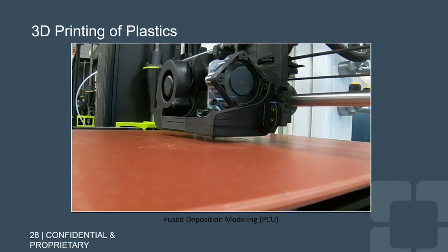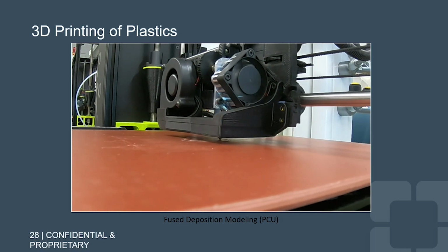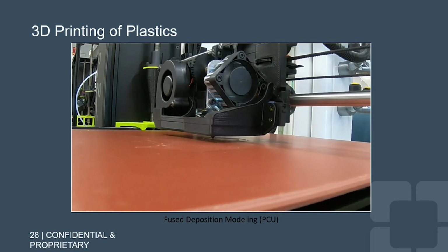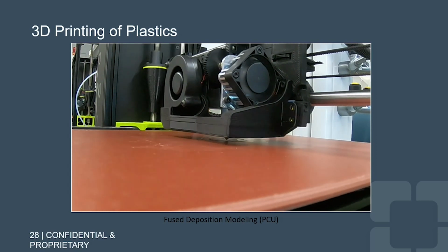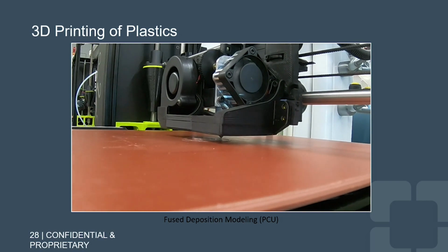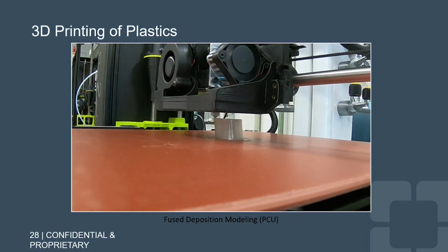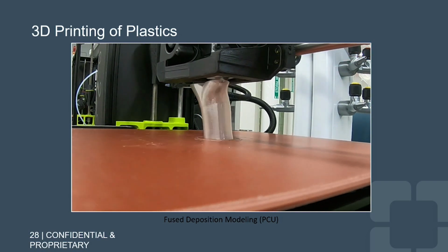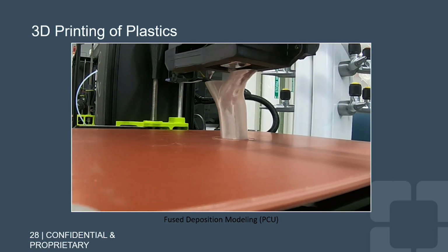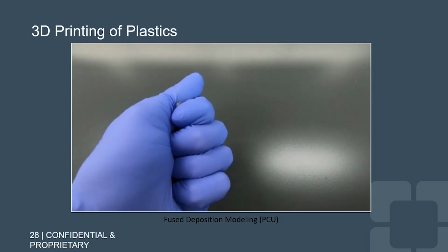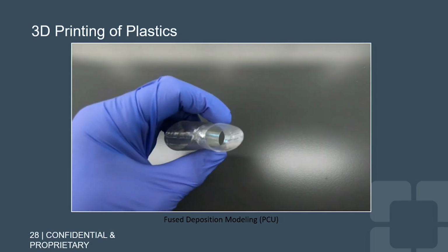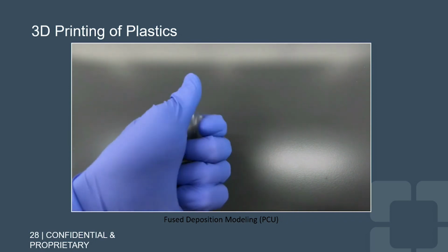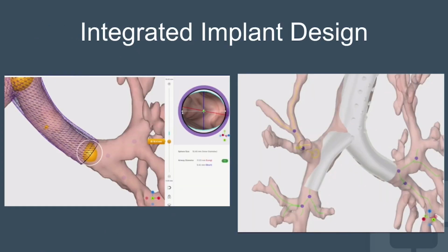And you can see in the future, we're hoping to get to direct 3D printing. Right now, the FDA allows us to do pressure-injected molded silicone. This, however, I think is polyurethane, and this is just a sped-up version of a 3D printer making the stent directly. And so I'll just let this play out for a second. One of the reasons we can't make silicone directly is that it's an elastomer, which means it requires a curing process. You have to heat fix it, whereas this looks like 3D printed materials directly. The challenge, of course, is to make sure that they're light enough, small enough, and flexible enough to be able to deploy inside the lung. So there's just an example of one.